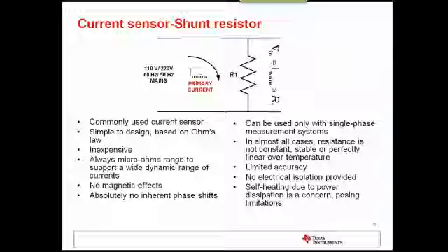Another advantage is that there's no magnetic effects with this type of current sensor, and there's absolutely no inherent phase shift. Some disadvantages are that it can only be used with single-phase measurement systems, and since the resistance can change during self-heating, this can affect accuracy at larger currents.